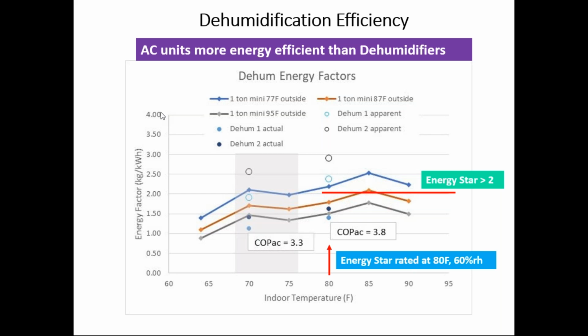to about 1.5. Now, the lines that are plotted on this are the energy factor of, say, a Minisplit air conditioner that I just showed. And you can see that as a dehumidifier, it compares very well to the adjusted dehumidifier that has to have its heat load adjusted out.